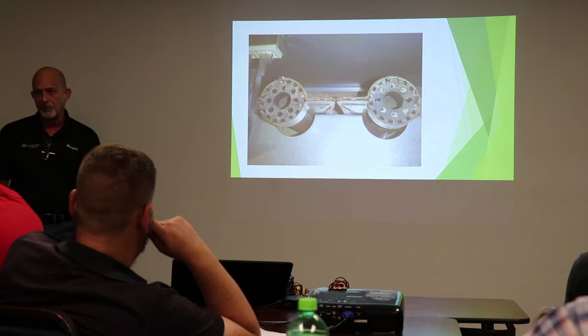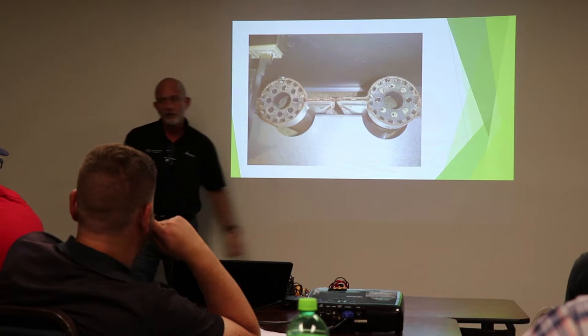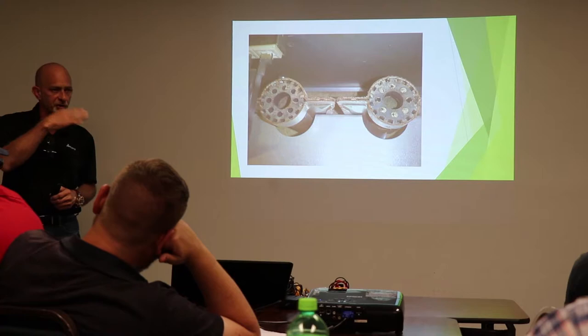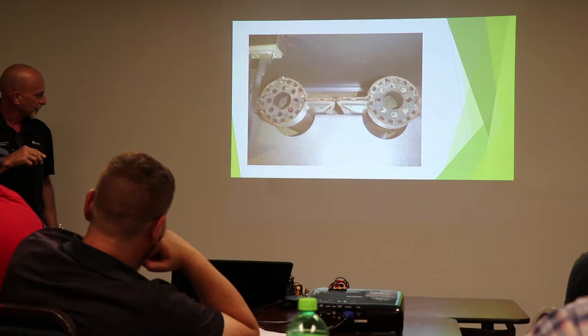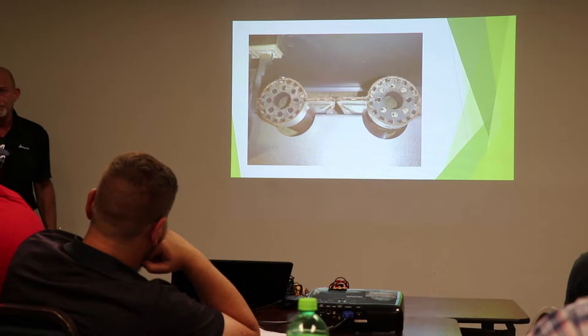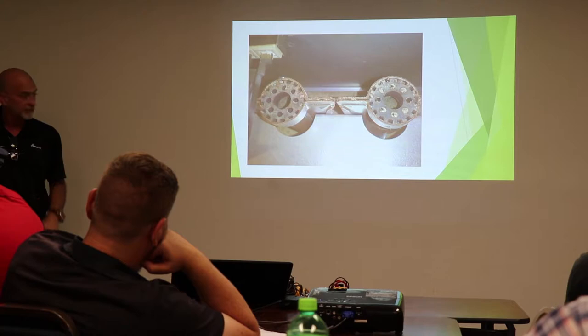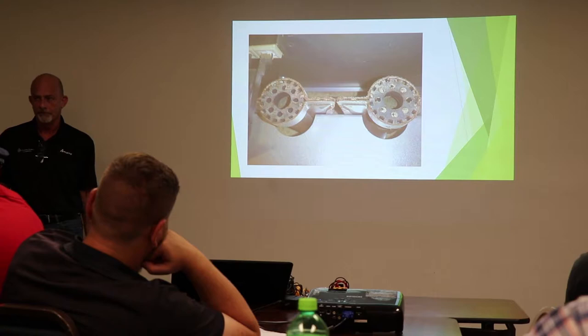Check our burners when we pull them out. Okay? Check our crossovers. If you don't know how an inshot burner works, it uses those crossovers to go to the next burner. Our fire actually comes out of here. Air comes around here. So what's this one doing? It's kind of plugged. That one's not burning too good. Now, eventually, they'll all light, even with crossovers plugged. And when they do, you hear it. Because remember, we go three-time trial for ignition. Maybe on that third time, we got enough gas built up across there. When it goes, it lights.